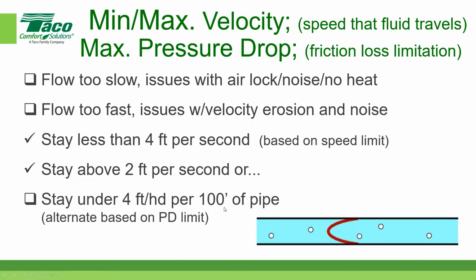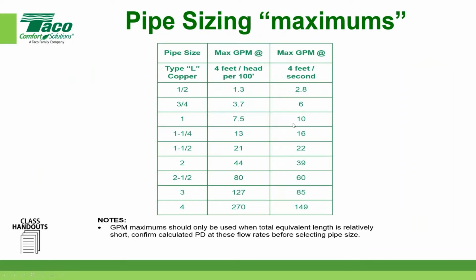What we're saying here is that the resulting pressure drop, if I ran a certain gallon a minute through that size of pipe, would be 4 foot of head. So again, it's the resultant pressure drop based on that type of pipe, based on that size of pipe, and based on the GPM running through it. So it's not as intuitive, but it is for the engineering community, and I'll show you how to interpret both of those. Here's one of them showing those.